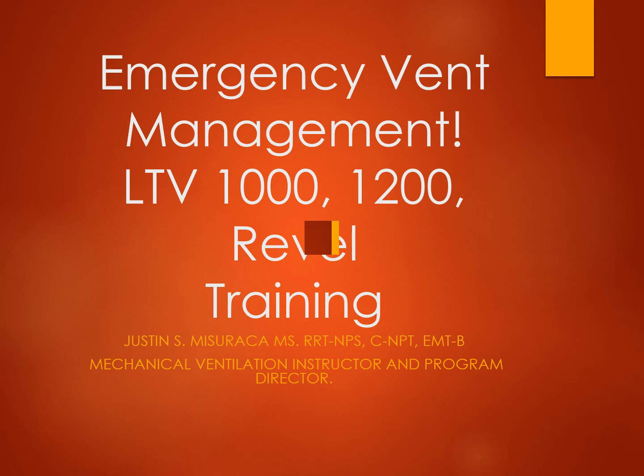So now I'm going to set the pressure support at 10 to give me 5 centimeters of water pressure. So remember that as you're going up on your PEEP, you're actually cutting into the pressure that's there. Otherwise, you'd be giving a pressure support of 0 and not knowing it. All right. So pay very close attention. If you have the LTV 1000, anytime you're dialing in a PEEP externally, pay very close attention to what your other settings are on there and what they're actually doing. All right. Moving on.